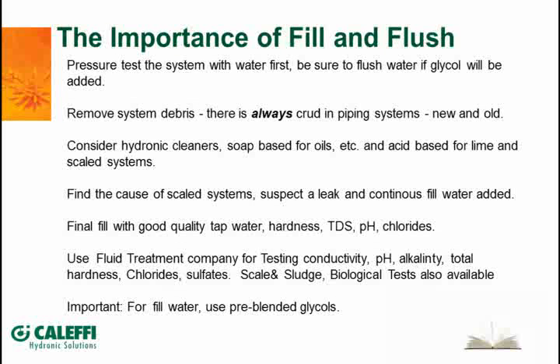That's typically, if it's on a domestic water side, going to be an acid-based type of cleaner that'll go in there and get that hard scale buildup off of your heat exchange surfaces. But now if you find a system like that and you open it up and you're retrofitting the boiler and you see that you've got some of that white, hard mineral buildup in there, you want to find the cause of that, because it didn't go in there the day you put it in. So usually you're going to find that there's a small leak in the system.